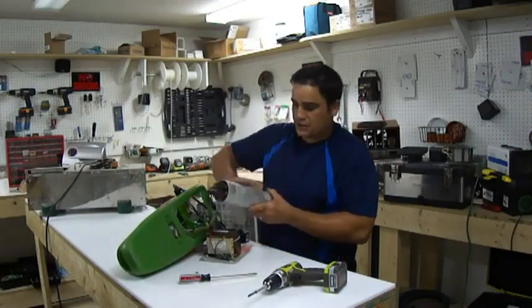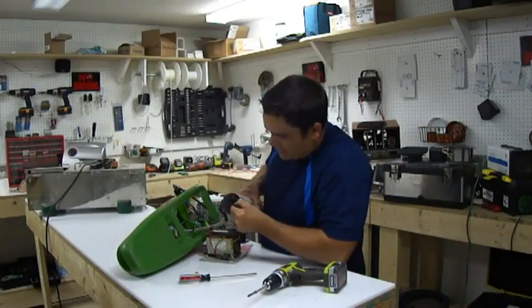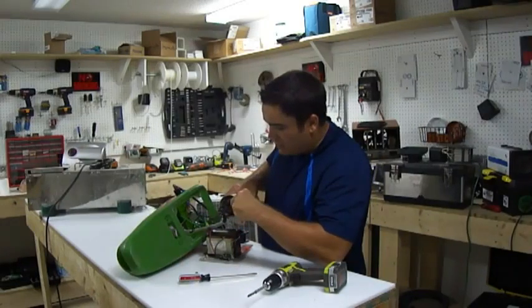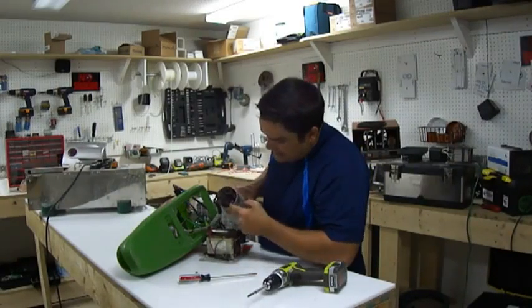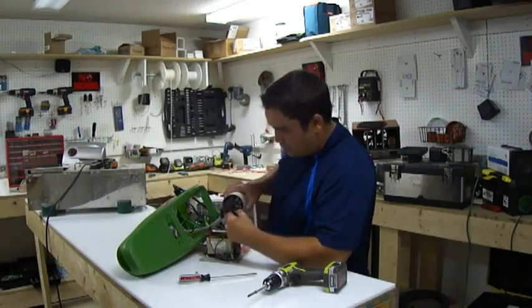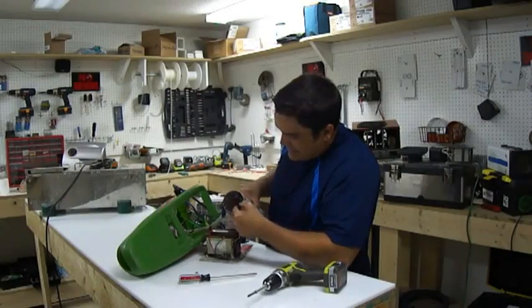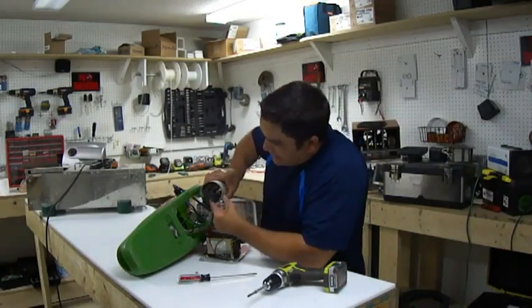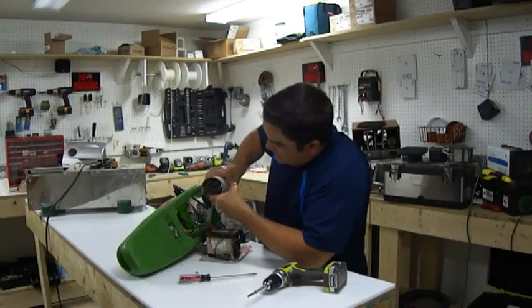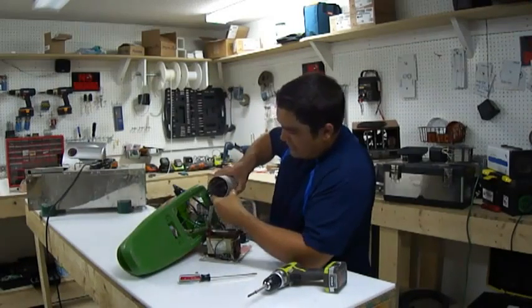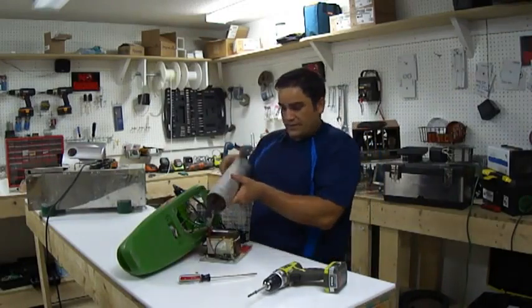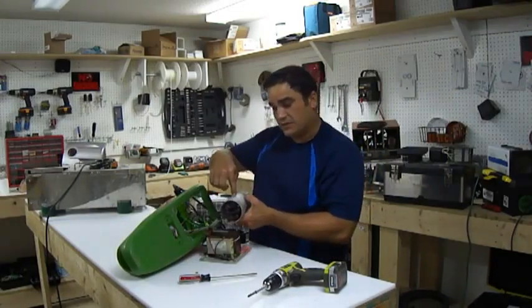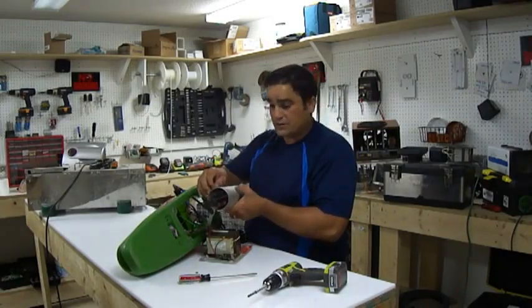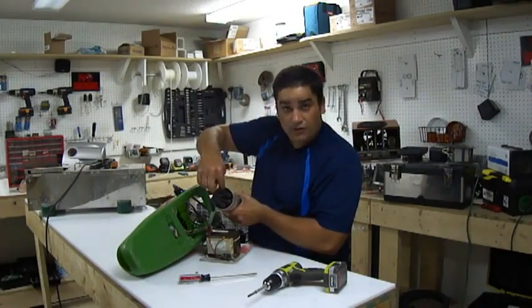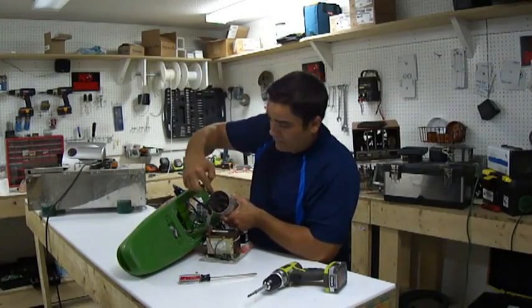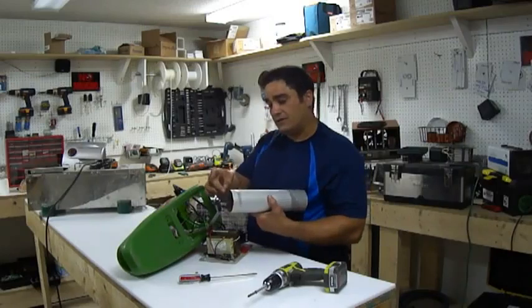Inside of this machine, folks, is an assembly that has a rod going through it, and then it has a piece of ceramic tube, much like a spark plug. It also has this piece of bent perforated aluminum to give extra surface area. That aluminum is contacting a ring, which contacts this aluminum ring, which goes to the ground wire. So we have high voltage electricity going through the rod, the ground is the perforated aluminum on the outside, and the dielectric medium is ceramic.